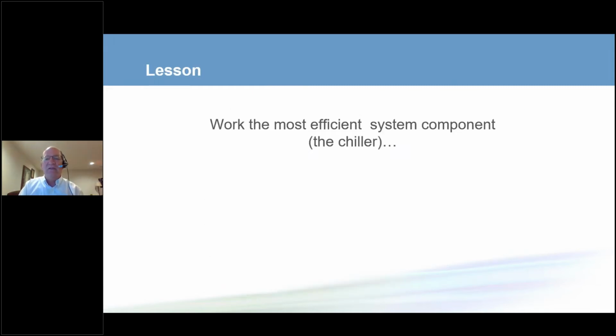And what this tells us is our lesson: take that most efficient part of the system. A chiller has a COP, a good chiller has a COP of around 7. If a pump is 70% efficient, its COP is 0.7. So a chiller is about 10 times more efficient than the pump. So let's work that most efficient part of the system a little bit harder. That's what the ASHRAE GreenGuide tells us to do.